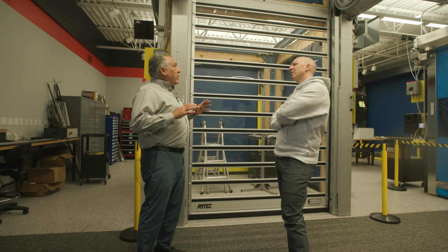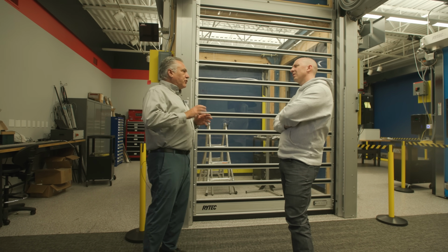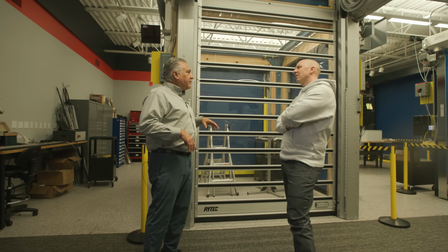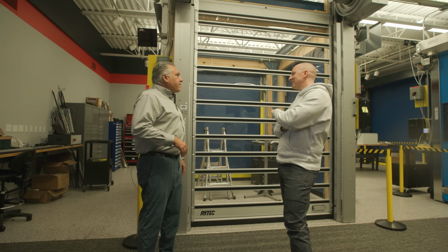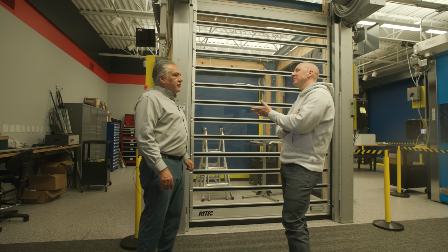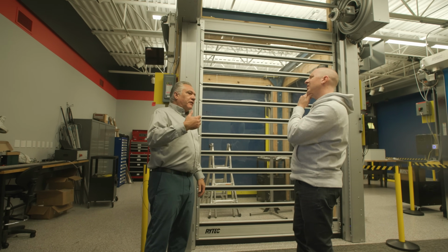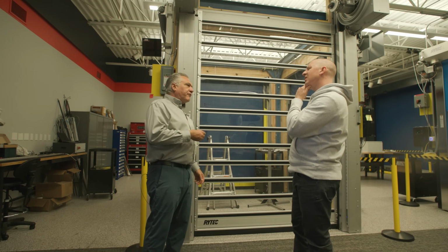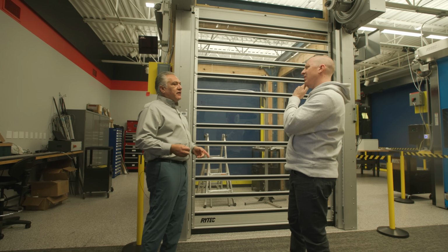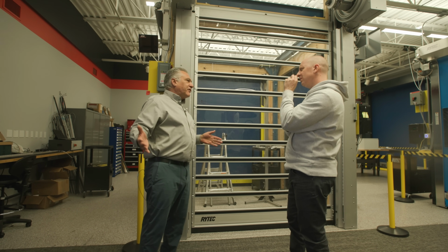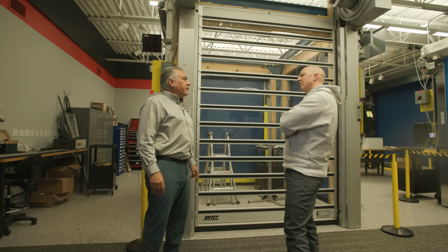So we actually bring the door to a stop without using any brakes. There's no friction involved in stopping the door. It's all done through the inverter drive system. Oh, wow. So it drives it and then just cuts power, basically. Or ramps down power. Our System 4 controller has what's called an inverter, an AC drive, or a variable frequency drive. It's very similar to what you would use in an electric car. It's like the harder you push the gas, the more power it pours to the motor.